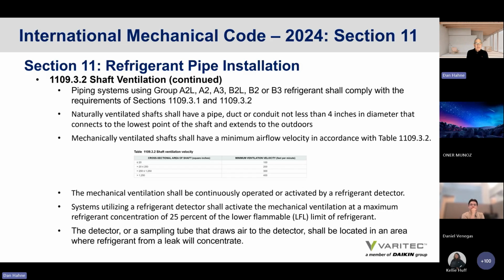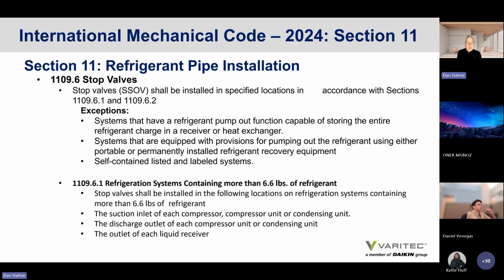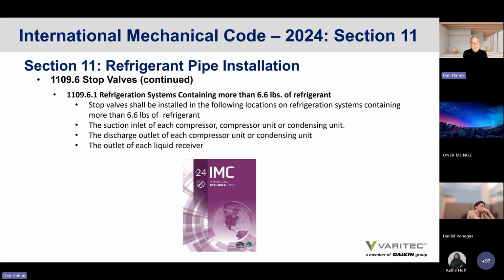And then there are refrigerant pipe installation requirements, such as naturally ventilated shafts shall have a pipe, duct, or conduit not less than 4 inches in diameter that connects to the lowest point of a shaft that extends to outdoors. Mechanical ventilation shall be continuously operated or activated by a refrigerant detector. Systems utilizing a refrigerant detector shall activate the mechanical ventilation at a maximum refrigerant concentration of 25% of the lower flammable limit of the refrigerant, etc., etc. It also has language on stop valves or safety shutoff valves and how they're to be applied.